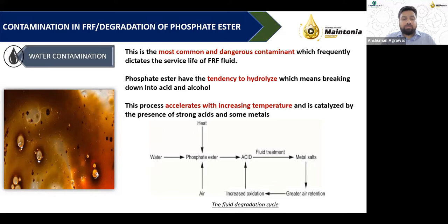It has been seen at a lot of plants where phosphate esters have been used: once the control valve fails, a blame game starts between the professionals. A lot of people start blaming the valve manufacturer, a few blame the instrumentation people, and a few blame the operations guys.